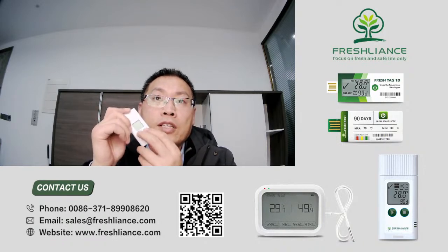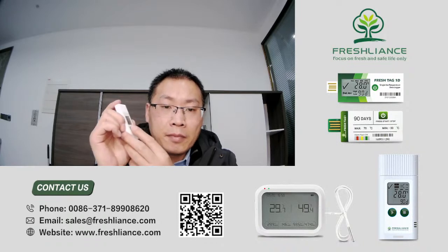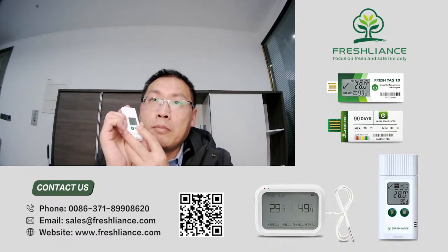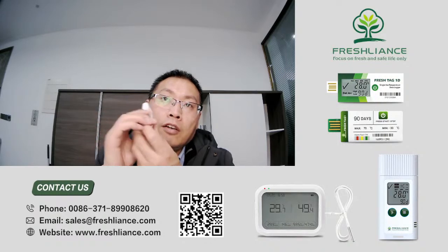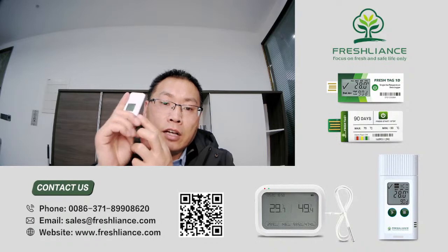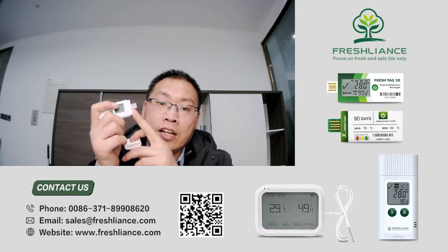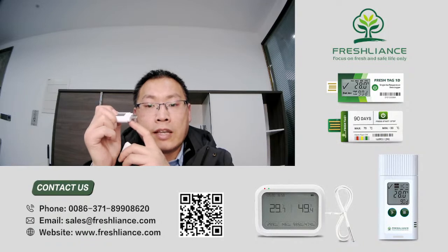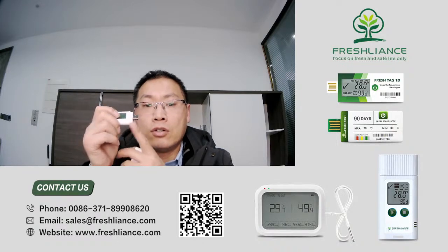Then, when the recording is finished, you can stop the logger by hand. If you want to stop the logger, just press the left button for 3 seconds. Then the maximum and minimum values will display on the screen. When the data logger is stopped, just open the cap at the top, and you can find the USB connector. Just plug the logger into the computer. You will get a PDF or CSV format report automatically without additional software.